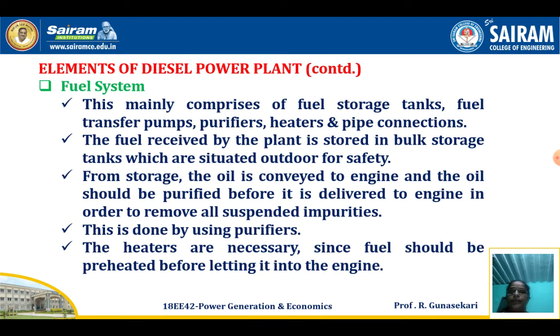Then fuel system. The fuel system mainly comprises fuel storage tanks, fuel transfer pumps, purifiers, heaters and pipe connections. The fuel received by the power plant is stored in bulk storage tanks which are situated outdoors for safety. From storage, the oil is conveyed to the engine, and the oil should be purified before it is delivered to the engine in order to remove all suspended impurities. This is done using purifiers. The heaters are necessary since fuel should be preheated before letting it into the engine.